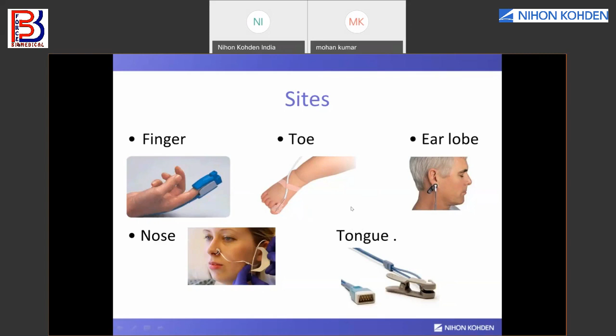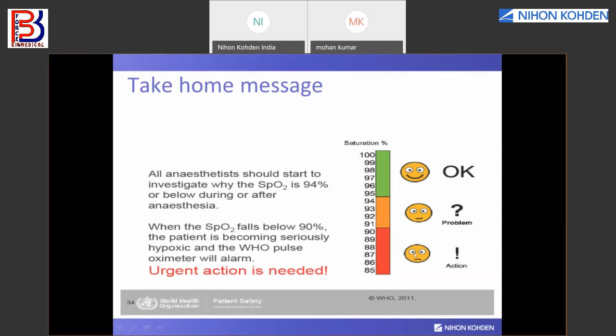So today's takeaway message is, as I told, SpO2 is a vital parameter. If the SpO2 reading ranges from 95 to 100, the patient condition is okay. Ideally, it should be 100%. If the values are between 95 to 100, the patient is doing good. If the values fall below 95%, then there is some problem which needs to be addressed. If the SpO2 reading goes below 90%, then immediate action has to be taken, and the patient has to be diagnosed for the next course of action.